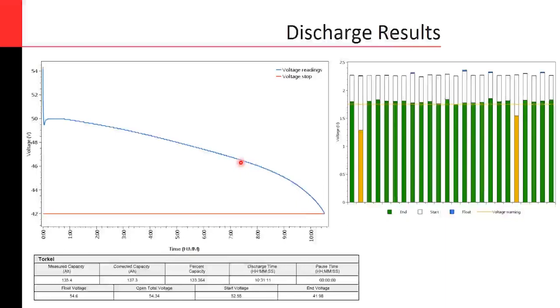And again, this is the voltage here. The full bar indicates the voltage at the beginning of the test. The green or yellow bar shows the voltage at the end of the test. The yellow line across the bars is the minimum value, the 1.75. So we see that at the end of the test, the battery still had some voltage, and basically these 2 cells probably caused the test to end a little earlier than it might have if those 2 cells were in good condition. Still, you have a good battery, but 2 cells are questionable.